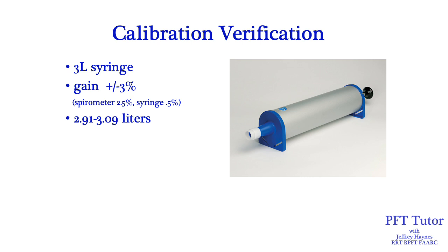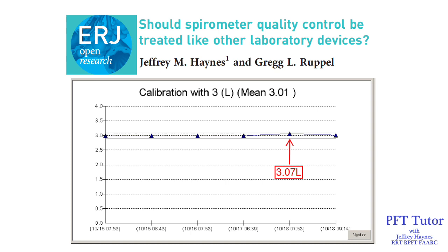I believe it is a myth, however, that if you do cal verification and your recorded values fall within the plus or minus 3% range, that means there is nothing wrong with your spirometer and everything is working fine. This is a case we had published in the European Respiratory Journal Open Research, asking whether spirometer quality control should be treated like other laboratory devices. One morning in my laboratory, I was doing cal verification and I got a reading of 3.07 liters, which is within the standard 2.91 to 3.09 range recommended by the ATS-ERS standards.